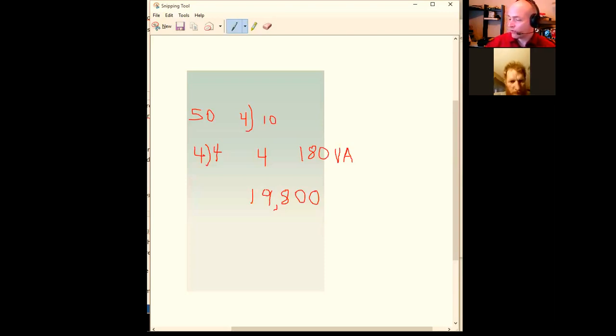If you look at K1, flip back to K1 real quick. K1 tells you that in banks and office buildings the load is calculated as the larger of either 1 or 2. Well, section 1 is exactly what we just did on the screen. It's taking 180 volt-amps, and then under section I, I'm permitted to take the de-rate. In this case, I would take the first 10,000 at 100%, and that leaves me with 9,800 as the balance, which is the amount I can take that 50% de-rate against. So 9,800 divided by 2 is 4,900. The 4,900 is added back to the 10,000, which gives you 14,900 as the de-rated value.